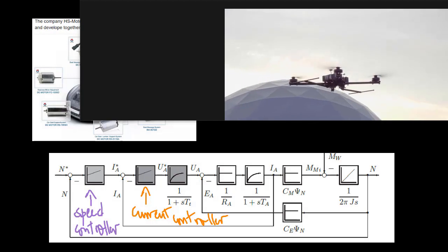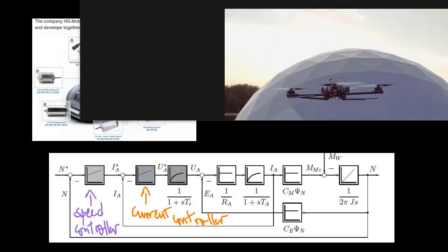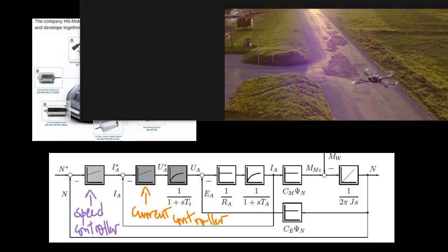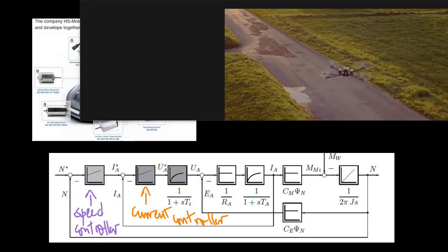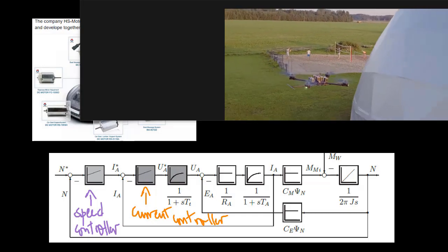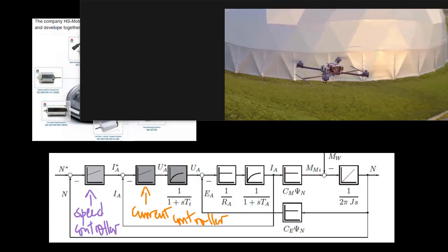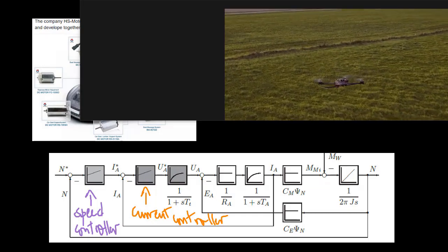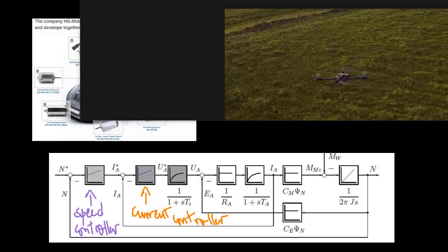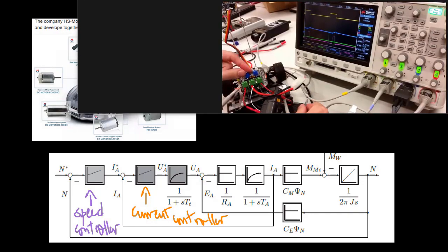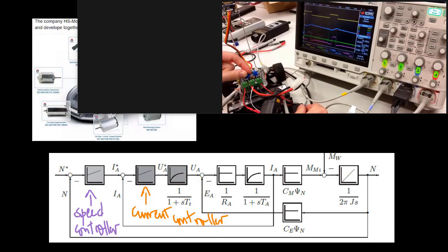The purpose of the first control loop, as described in the last video, is to determine the setpoint of armature current according to a comparison between actual speed and target speed. The purpose of the second control loop is to secure the armature current setpoint, and in doing so, secure the target speed.